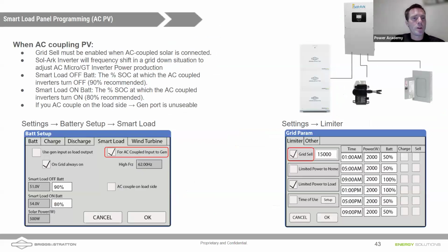Certainly possible. We also need to program that generator port to let it know that, hey, we're using this gen port for AC coupled solar. And so we're going to have this box checked here. And then if you've got the grid on, you'll be able to send that excess power back to the grid by enabling grid sell. So I normally would have this box checked for when the grid's on, the AC coupled solar is always on, and that way any excess power from the AC solar just feeds back to the grid. But in a grid down situation, once those batteries fill up, we want to turn off that AC coupled solar and let it coast off the batteries for a while.